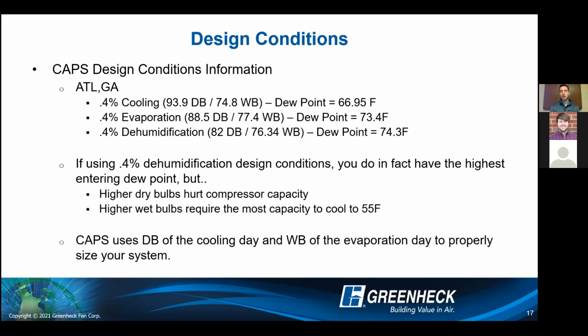Another unique thing I want to talk about related to cooling is design conditions. So with the design conditions, I want to specifically look at the Atlanta, Georgia market. Generally, what we're seeing is ASHRAE 90.1, the 0.4% weather bin data is generally what's used to design DOAS style equipment. So obviously, there's a number of different ways you can do it. You can look at the 0.4% cooling, the 0.4% evaporation, or I would say what we see a lot from other manufacturers, or maybe what you're using right now, is 0.4% dehumidification. Obviously, DOAS is meant to bring in high percentage of outside air, dehumidify that. And if you look at the dry bulbs and wet bulbs, they vary pretty drastically, specifically on the dry bulb side. And you can see the dew point vary as well.